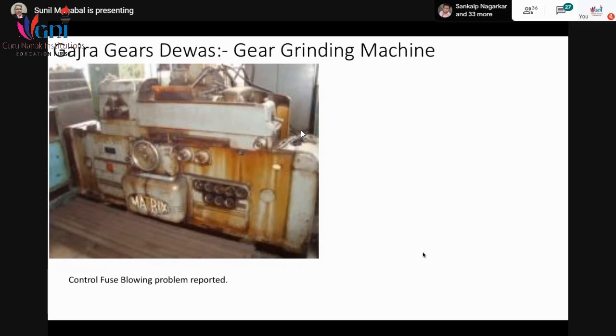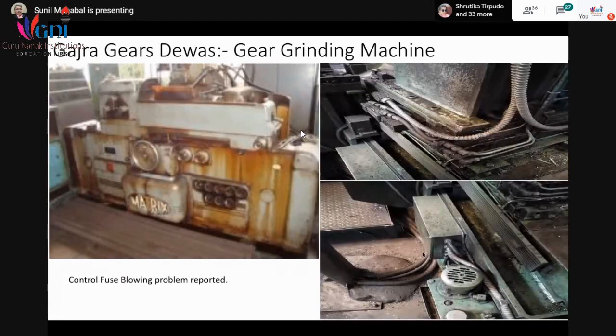So then we studied it and we found that there are many conduits which are carrying control wires inside them. And these conduits have a metal wire also. The rest is plastic, but it has a metal wire also. So there will be 25 to 30 wires inside one hose or one flexible conduit. This is not the picture of that machine, but I am sharing how the condition of the flexible conduit looks in a working machine. Somebody can stumble on it, put a leg on it, or put some material on it. So there is a possibility that the bunch of wires going into this flexible conduit and then to the machine, some wire was getting shorted.